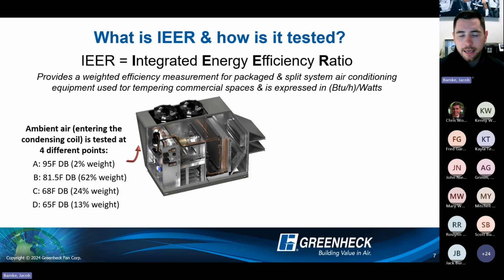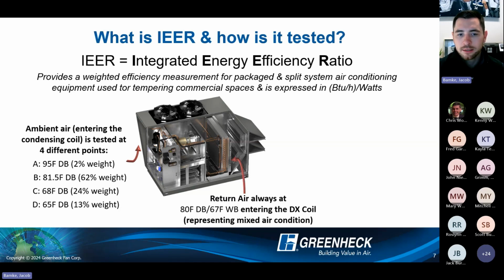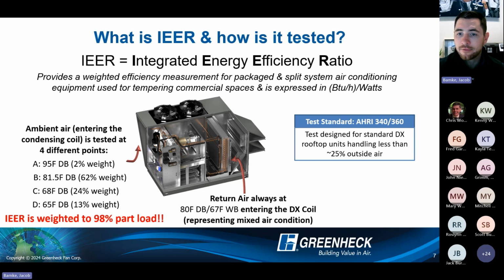What you look at with this IEER test is that in each one of these points, the return air never changes. So what's entering our indoor coil is always going to be 80-degree dry bulb, 67-degree wet bulb. So it represents a true recirc type application, or if we think about those VAV type applications. The other thing to point out is IEER is weighted to 98% part load conditions. So as our efficiency minimums continue to increase, we have to focus on what components are the most efficient during part load conditions, not necessarily full load conditions. And this is actually designed after AHRI 340/360. Typically that's for, again, 25% outdoor air and less.